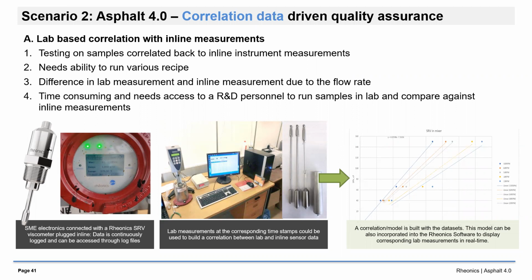The benefit is that SRV is a fantastic sensor for tracking any kind of change from that baseline, and that baseline is the number you got from the lab. So instead of the SRV just giving you 260 centipoise, it will also give you 1400 centipoise and the variation in it. It can go to 1460, it can go to 1500, it can come down to 1300. Depending on the limits you have, your operator can say, this is still within my limits. That is the main reason something like this can be done, and it is being done by some of the customers that use the sensor.